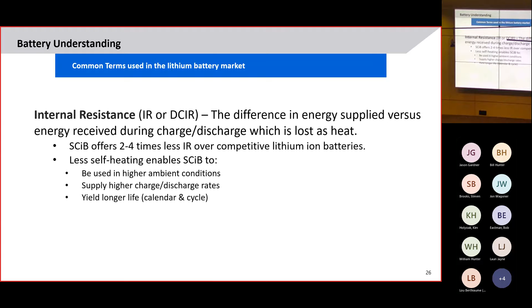In this case, we have a 6-month run for capacity and impedance, and as you can see, they're clustered together, which is the way you want your batteries manufactured. It offers lower internal resistance. The number one enemy for batteries is heat, so by lowering the internal resistance, you also lower the internal heat generated when charging and discharging those batteries. We're going to talk more about heat internally here in a minute.